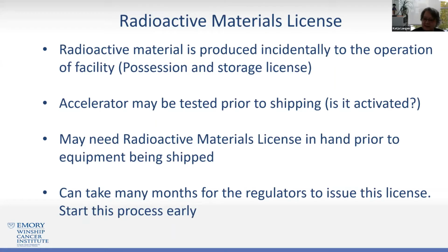Please keep this in mind because you may have to have the radioactive material license in hand prior to the equipment being shipped. It can take several months for regulators to issue this license, so please start this process as early as you can.